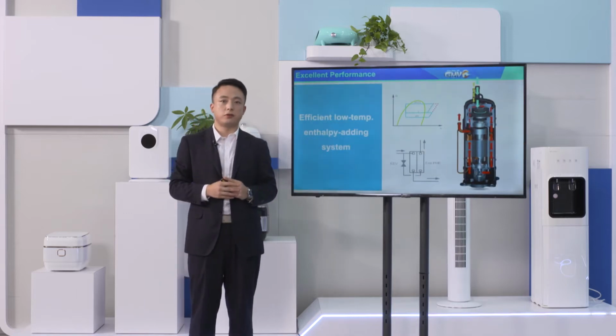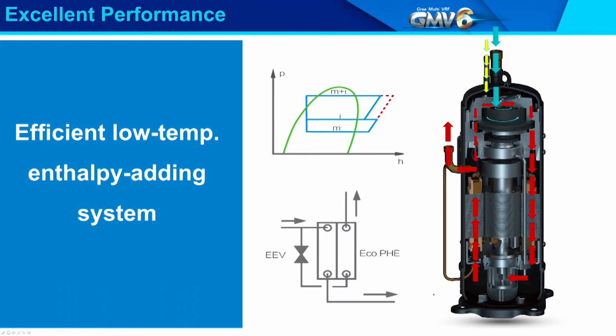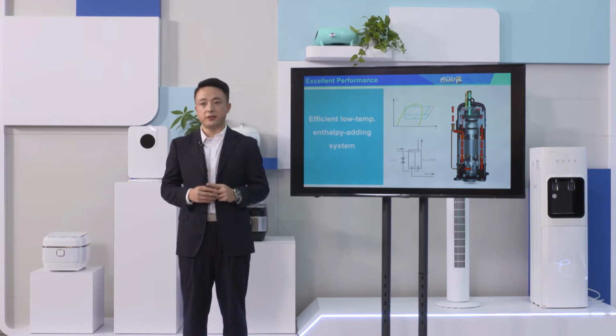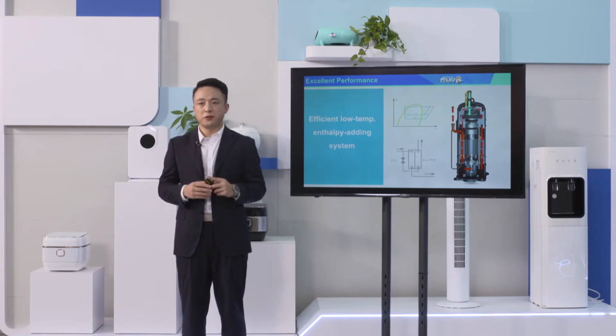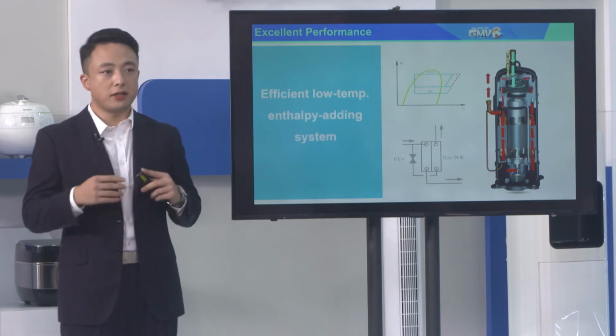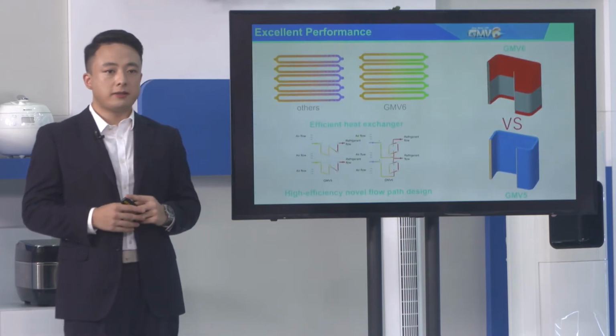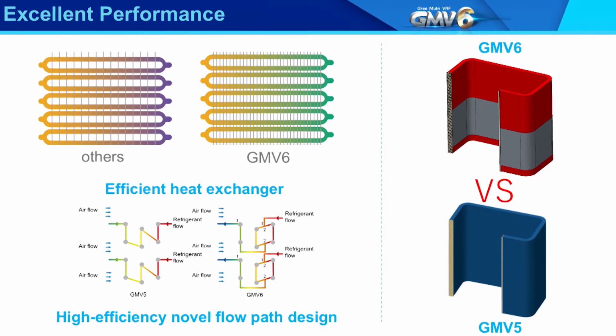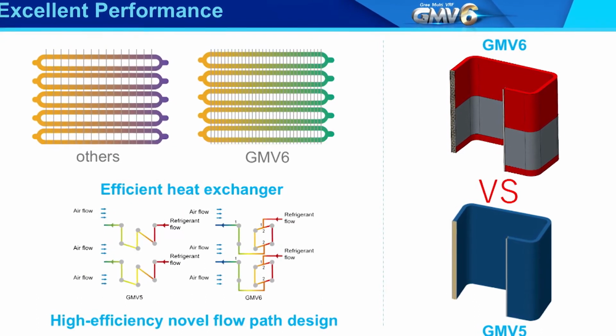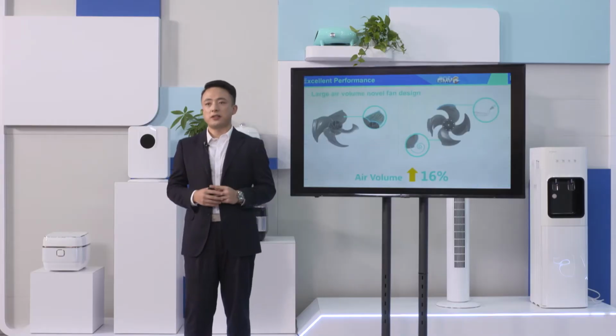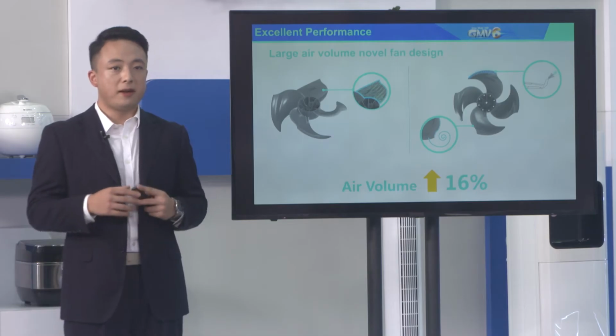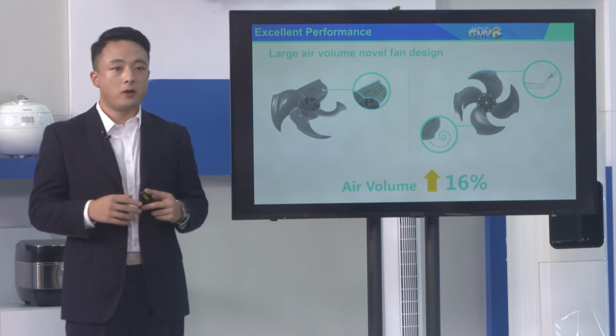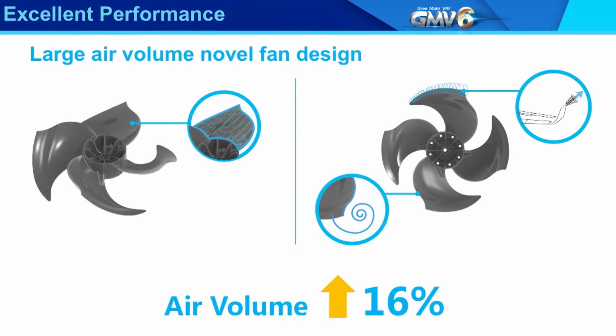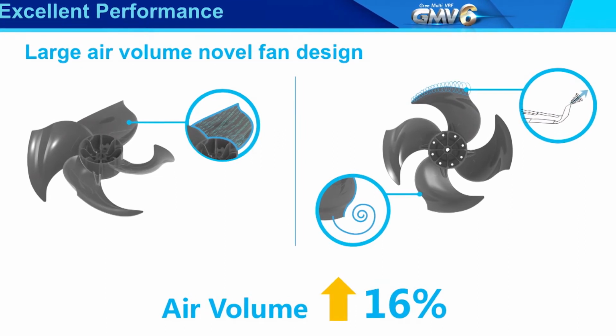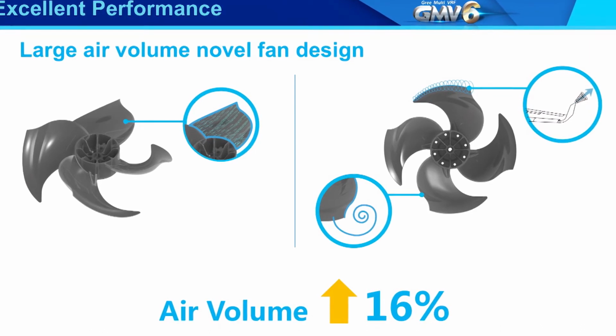GMV6 has 5 core technologies. First, excellent performance. As we all know, compressor is the heart of AC system. We adopt efficient low-temperature enthalpy-adding system, which is specially designed for VRF units and can improve cooling capacity and energy efficiency. The use of corrugated small-pitch heat exchanger fans and layered dual-zone heat exchange increases the heat exchange rate by 8%. The specially designed large flow air duct, optimized fan blade, and a new air outlet grill enable us to broaden the air supply area by 7.8%, so that the air volume of GMV6 enhanced by 16%.